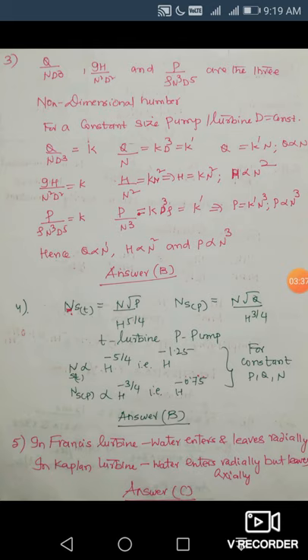Similarly, analyzing the head and power, H is proportional to N² and P is proportional to N³. So Q ∝ N¹, H ∝ N², P ∝ N³ — the powers are 1, 2, 3. Your answer should be B.